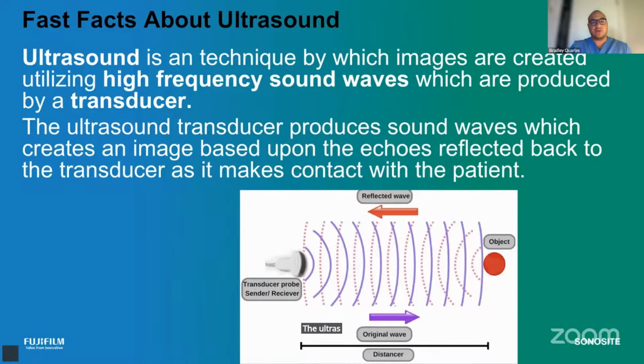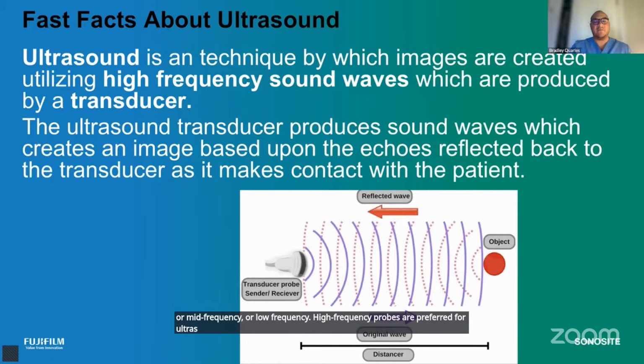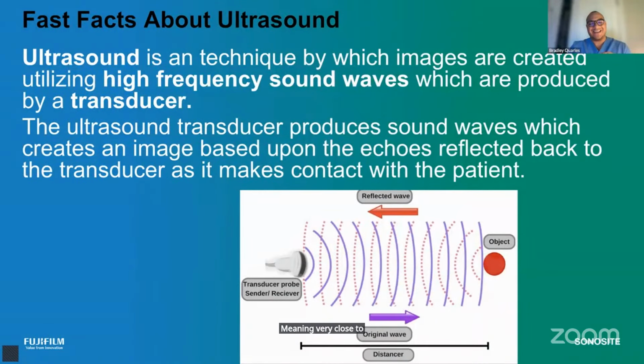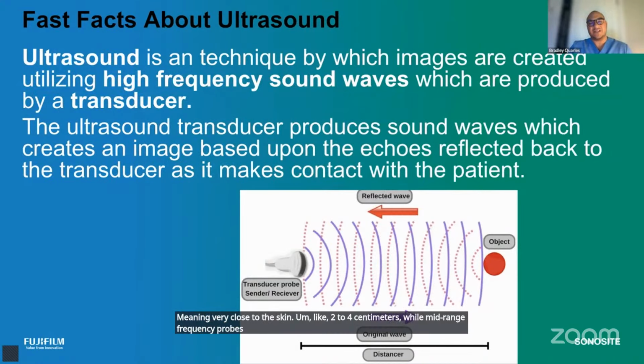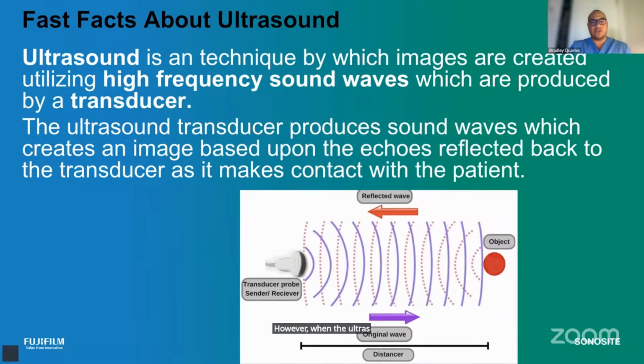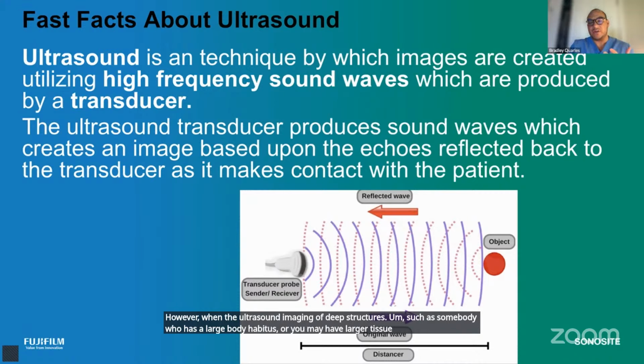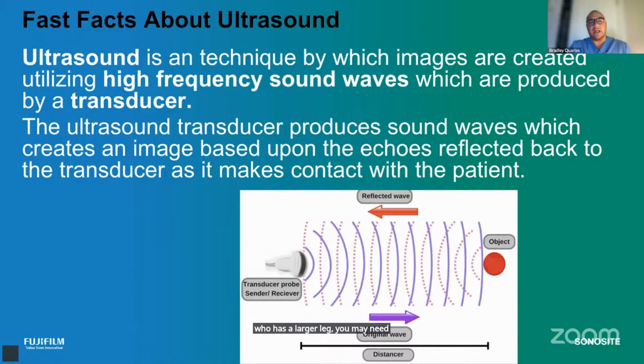The ultrasound transducer produces the sound waves, and they can either be considered high frequency or mid frequency or low frequency. High frequency probes are preferred for ultrasound images that are very superficial, meaning very close to the skin, like 2 to 4 centimeters, while mid range frequency probes are for slightly deeper structures that are considered like 5 to 6 centimeters. However, for ultrasound imaging of deep structures, such as somebody who has a large body habitus, where you may have larger tissue to traverse to view something, such as maybe you're doing an IPACK block or you're doing a popliteal sciatic block on somebody who has a larger leg, you may need a low frequency probe.